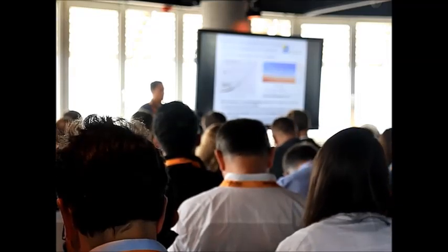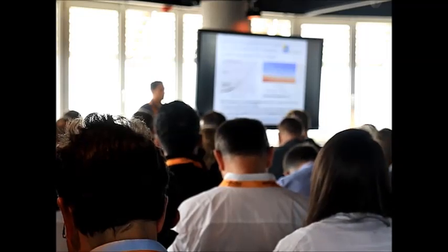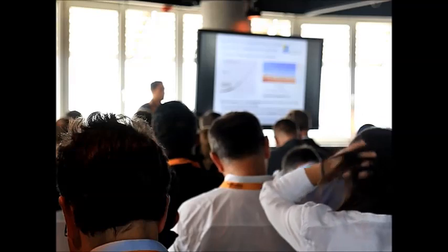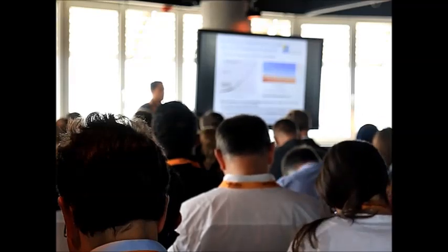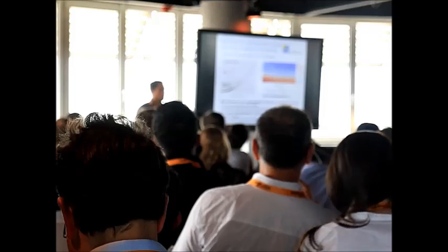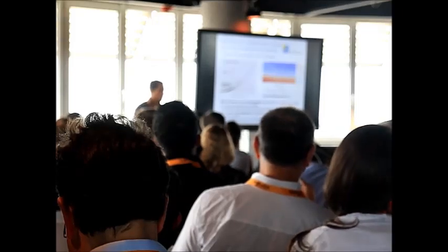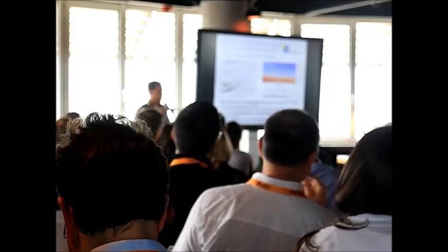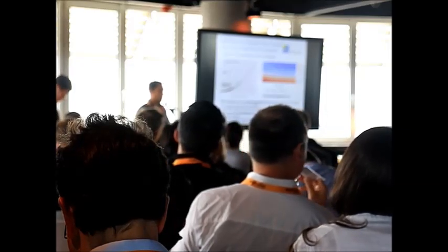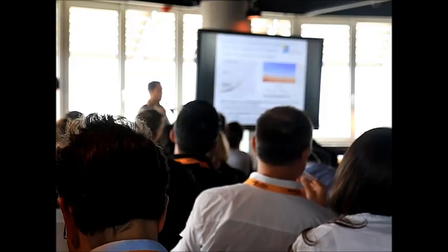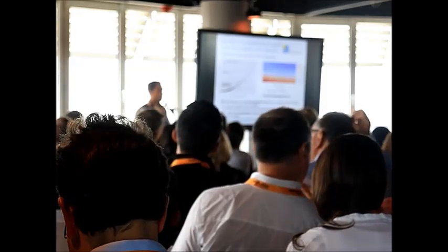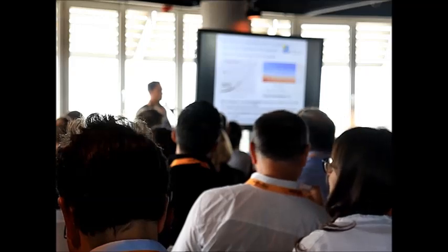So you will have almost the same losses with this gradient, because the bottom cells still perform worse, and you still have this gradient. So maybe you should think of something other than only making a module portrait, such as reducing or making a different interconnection of the cells inside the module. This is going to be a better solution to mitigate this mismatch.